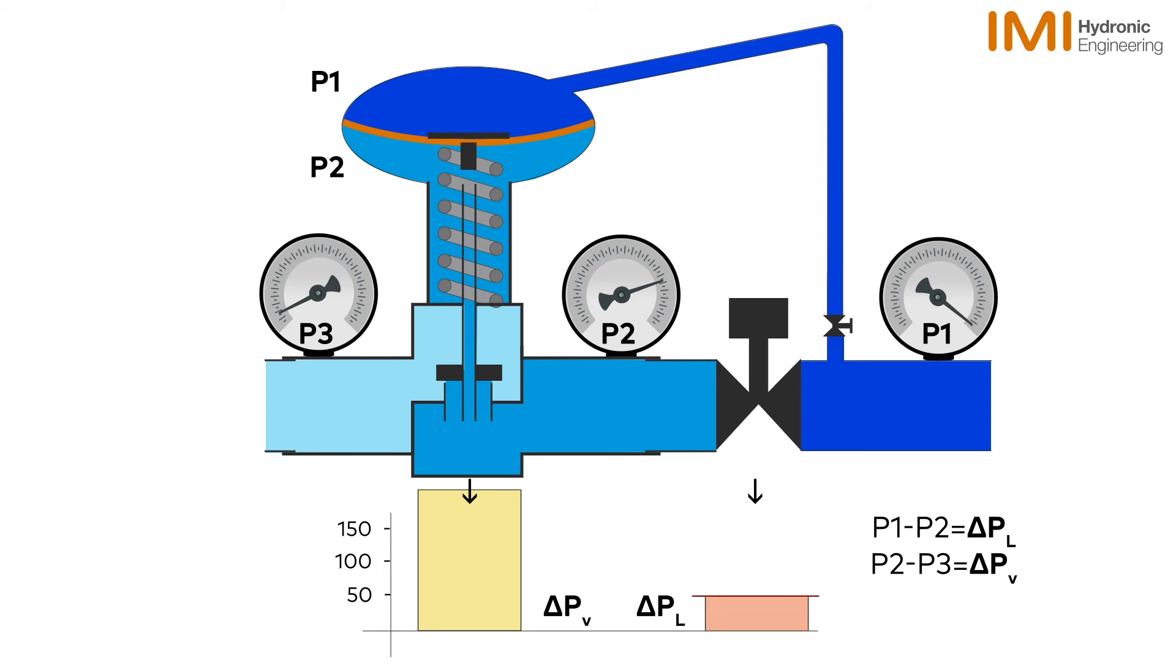Upon a decrease in available pressure P1 minus P3, the valve acts in reverse. Initially delta PL will reduce. The valve will then act upon this change and open to bring delta PL to set point and decrease delta PV proportionally.